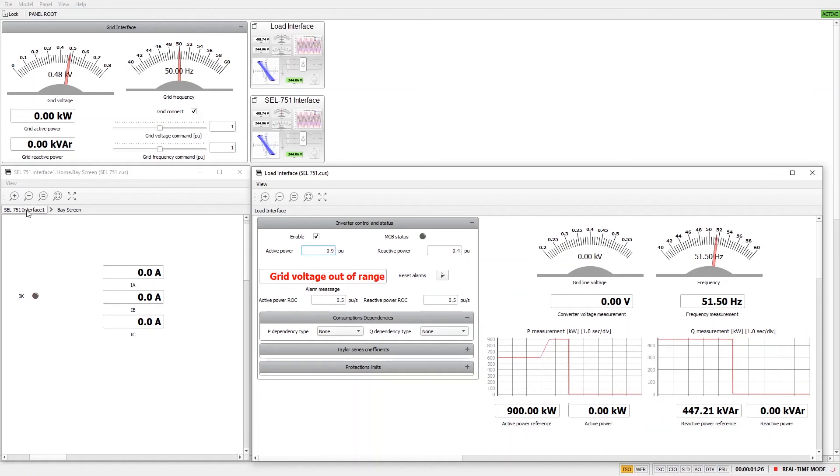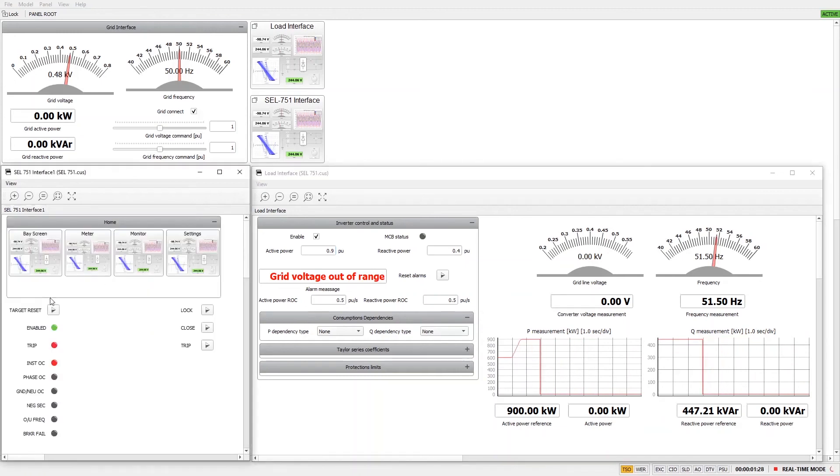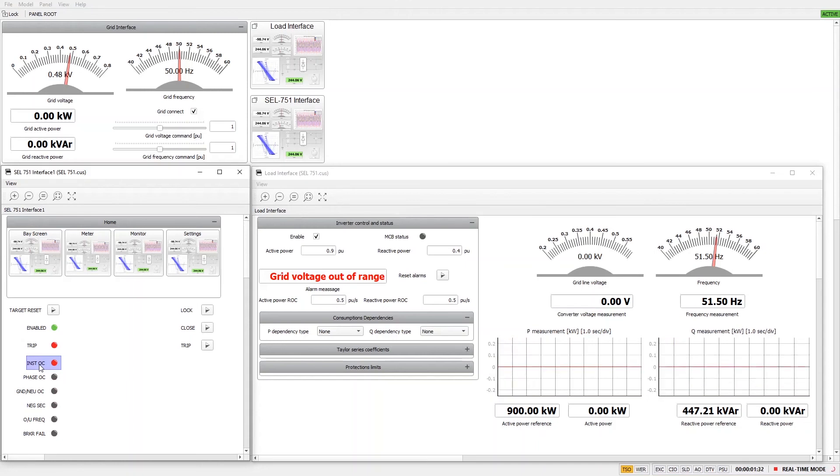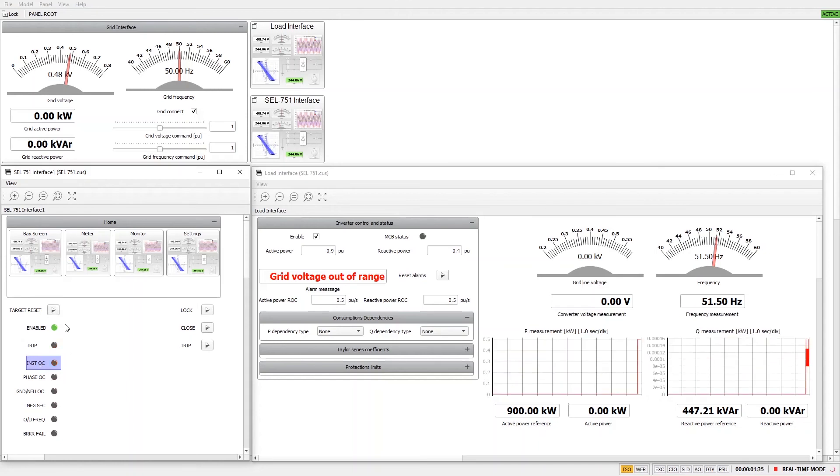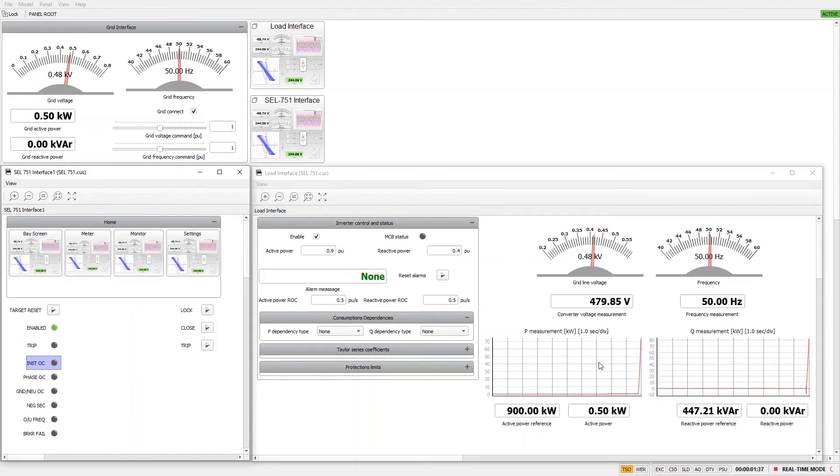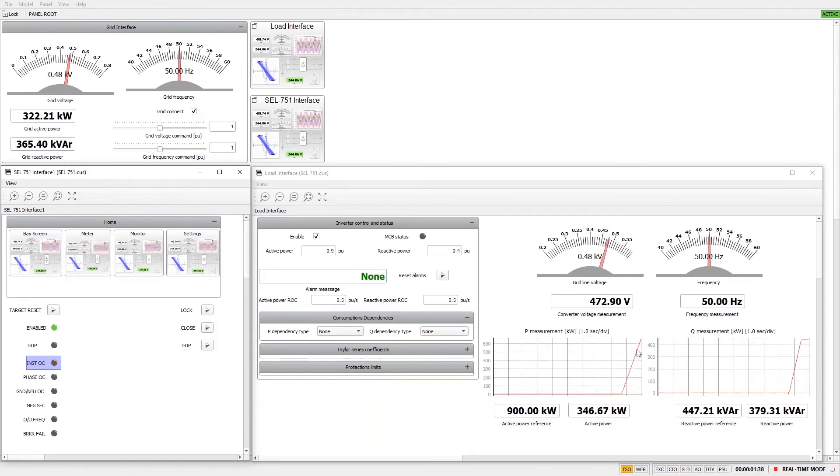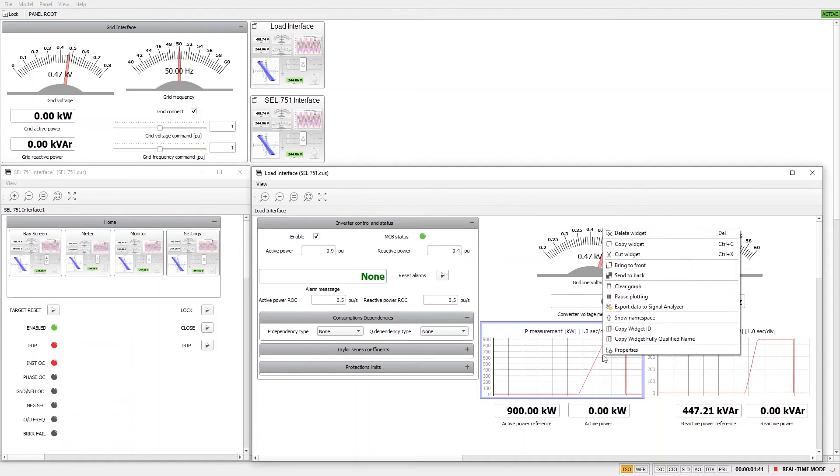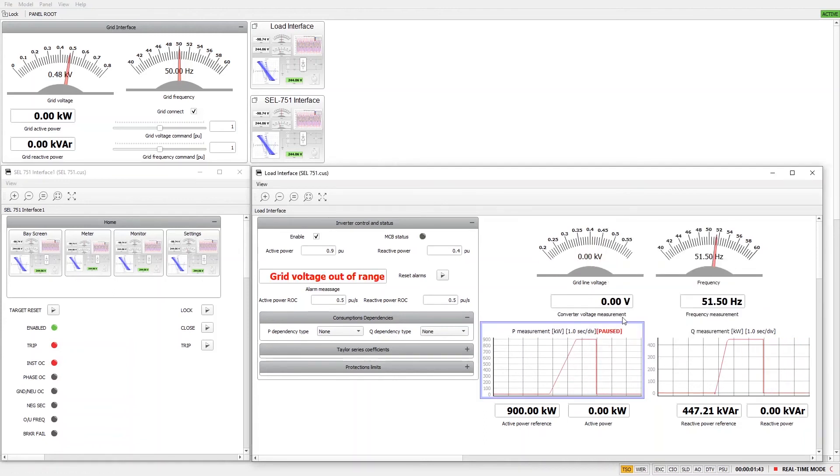If we go back to the SEL-751 interface, we can see that the instantaneous overcurrent protection has reacted. If we reset our relay, we can see that the load ramps up its power consumption back to its previous value and consumes the reference amount of power until the overcurrent trip delay of 1.4 seconds completes.